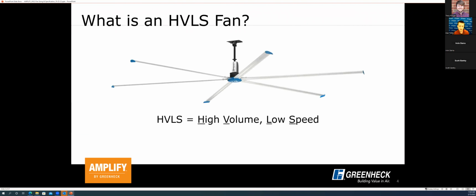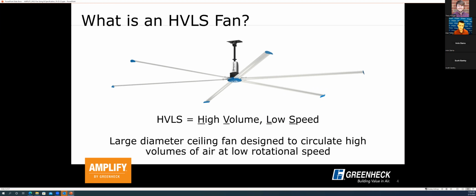These fans have only been around for about 20, 25 years, so they're still kind of a little bit new, with a lot of new applications still being discovered for this type of product. But what is it? What does HVLS stand for? HVLS means high volume, low speed, and essentially that name tells you exactly what this product is. It's a large diameter ceiling fan that is intended to circulate high volumes of air, the high volume part of the name, at relatively low operational speeds, the low speed part of the name.